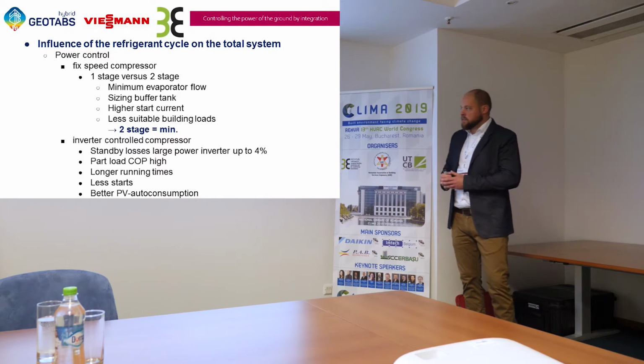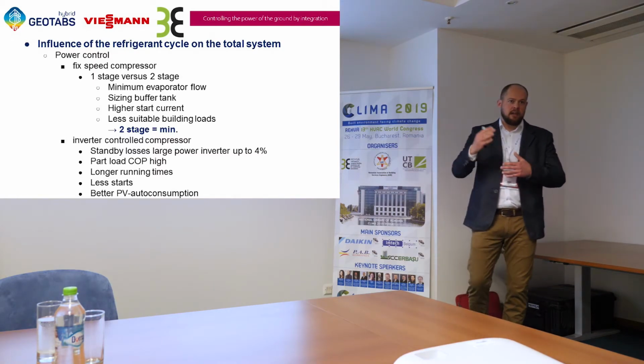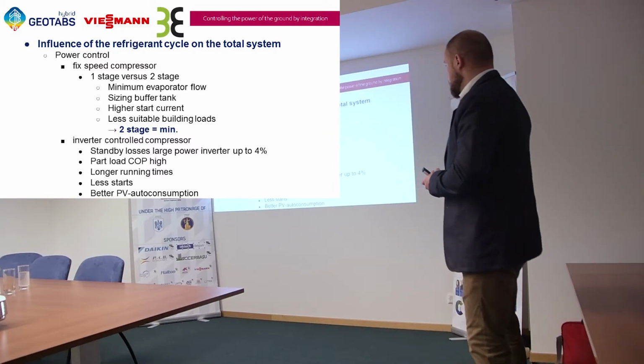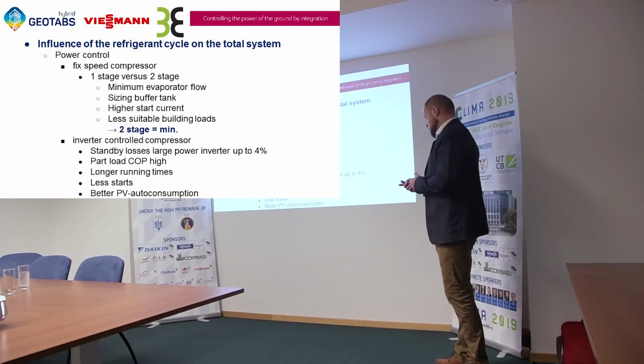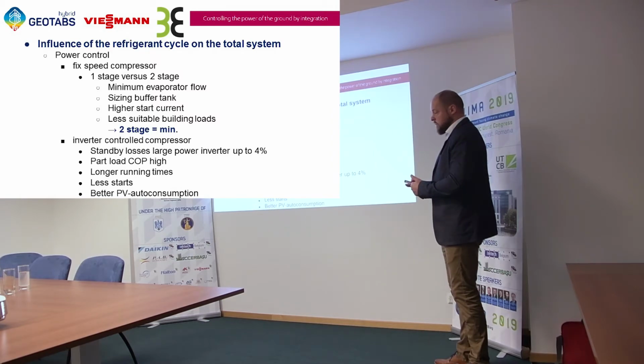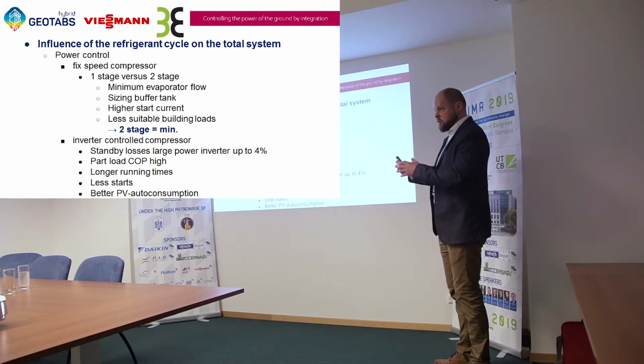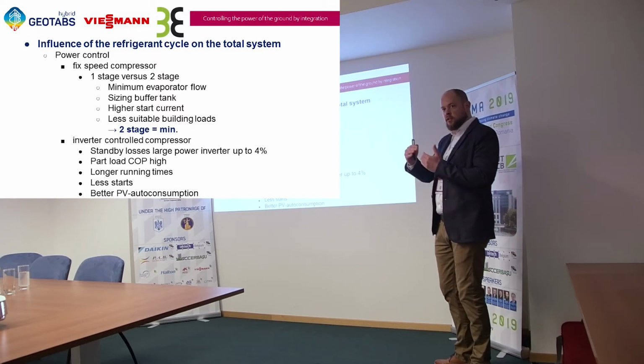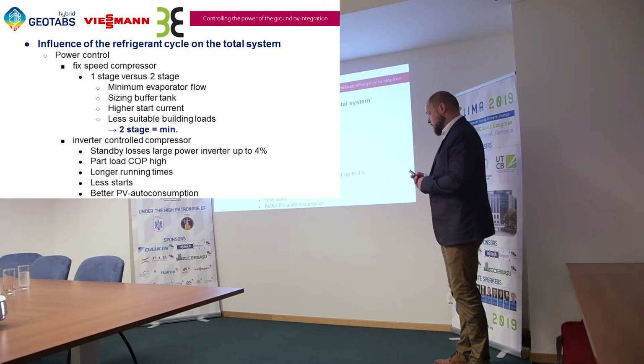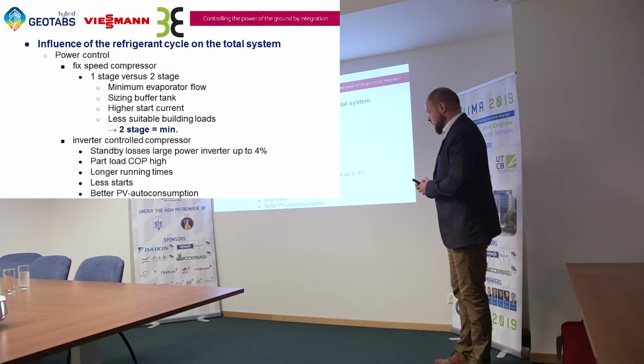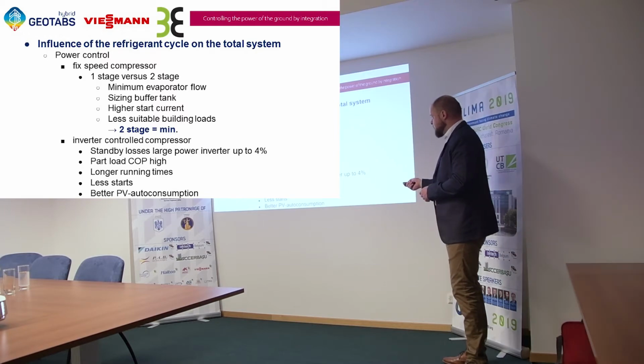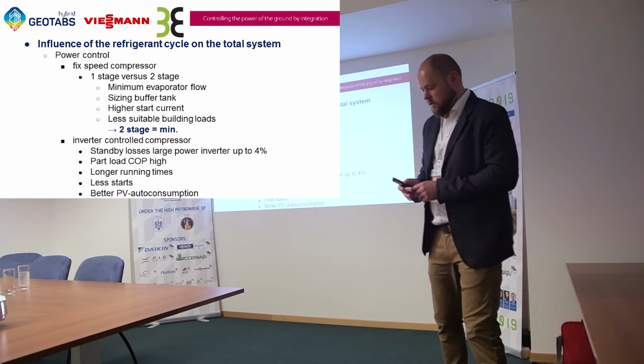A newer development is inverter controlled compressors. When we can regulate the rotation of each compressor, you can see the part load COP is very high. We have much longer running times, so that's much better, and we have fewer starts. Another benefit of this system is that when we have solar panels, we can easily use the energy produced by the solar panels instantly. We can follow the load on the production of these panels. The other side of the inverter control system is that we have a standby loss by the inverter, which can be up to 4% of the electrical load.